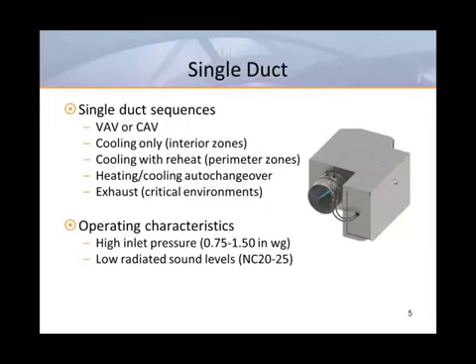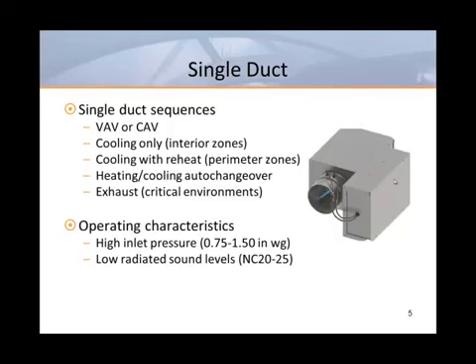If an air handler only supplies cooling, interior zones will use cooling only units while the perimeter zones would most likely use some sort of heat. In this situation, any heat located at the box would be reheat. The box controls could also be used to operate auxiliary heat, such as a fin tube heater or a radiant panel. When there's heat in the air handler, it may be necessary to provide auto-changeover controls so that the box can reverse its operation to provide both VAV heating and VAV cooling.